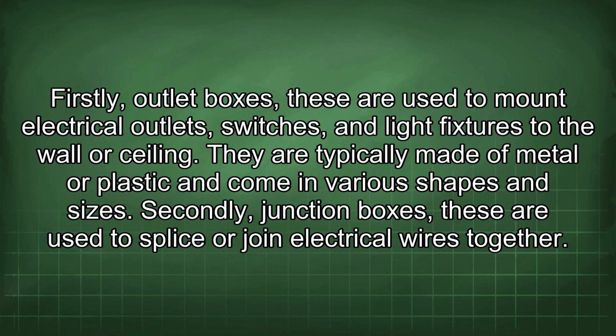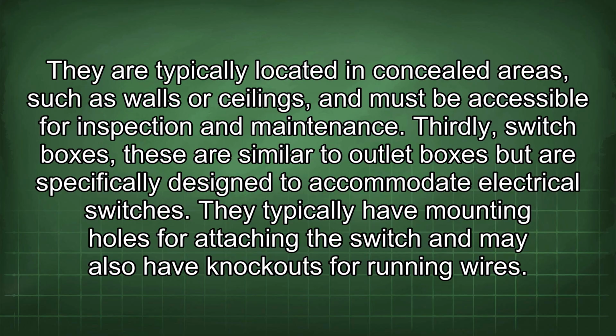They are typically made of metal or plastic and come in various shapes and sizes. Secondly, junction boxes. These are used to splice or join electrical wires together. They are typically located in concealed areas such as walls or ceilings and must be accessible for inspection and maintenance. Thirdly, switch boxes. These are similar to outlet boxes but are specifically designed to accommodate electrical switches. They typically have mounting holes for attaching the switch and may also have knockouts for running wires.